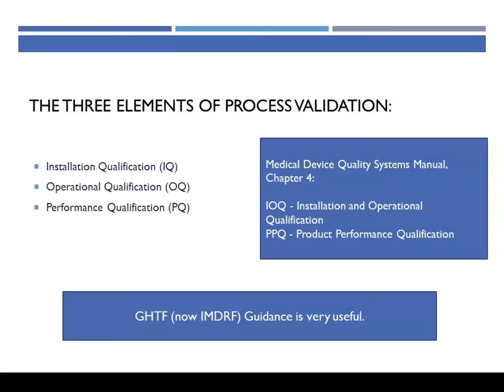Now, when we do validation activities, there are going to be some general documents that we're going to use, whether it's an IQ, OQ, or a PQ. We're going to write a protocol ahead of time. The protocol describes what it is we're trying to prove, why we're doing this. It provides all the detail on how to do the validation, what equipment is used, etc. And most importantly, it's the place where you put that predetermined specifications.